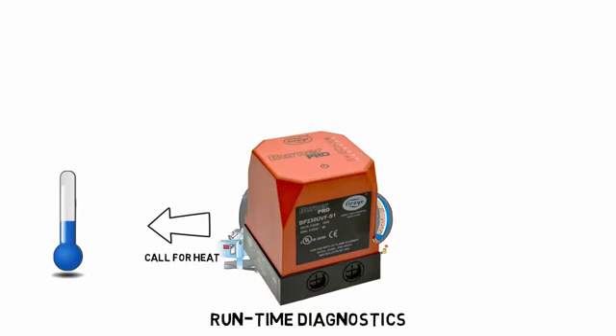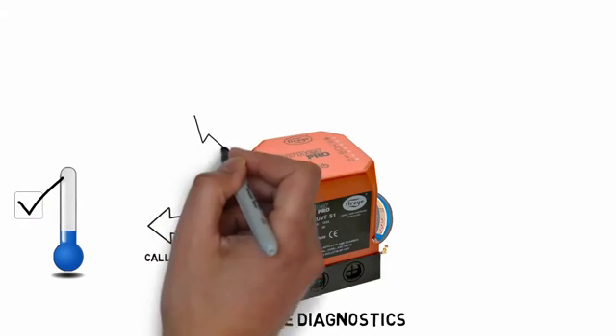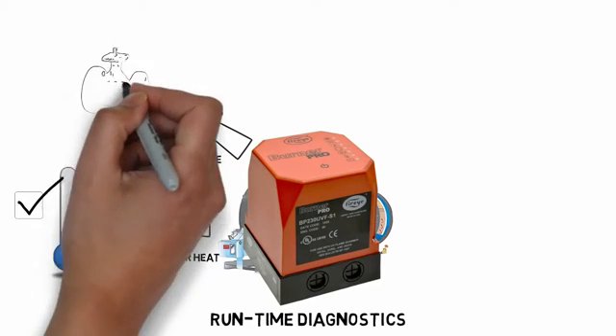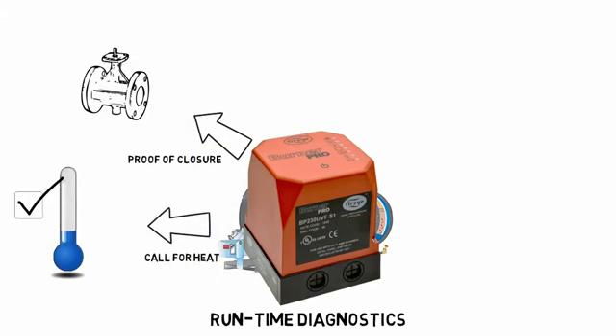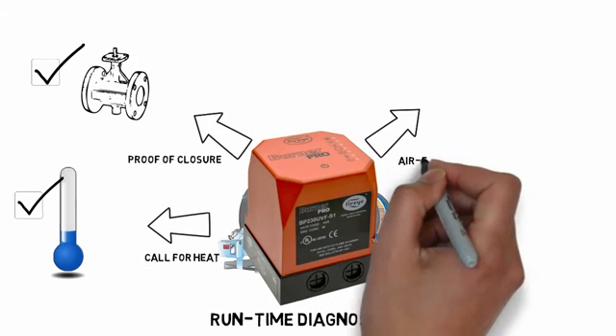Upon receiving a call for heat, the system turns on the combustion air blower and commands the actuator to move to the purge position. Proof of valve closure checks for wiring problems or faulty fuel valves. Air flow proving cycle ensures a proper combustion environment.